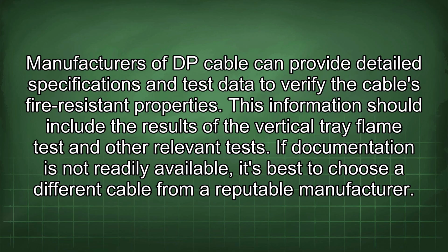Manufacturers of DP cable can provide detailed specifications and test data to verify the cable's fire-resistant properties. This information should include the results of the vertical tray flame test and other relevant tests. If documentation is not readily available, it's best to choose a different cable from a reputable manufacturer.